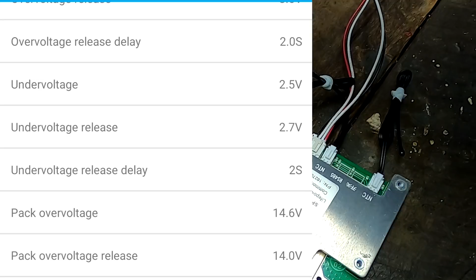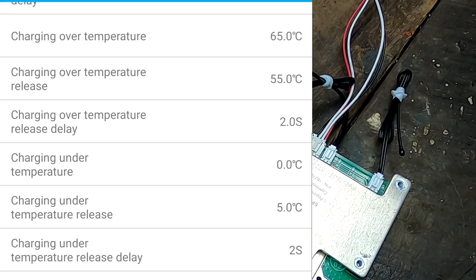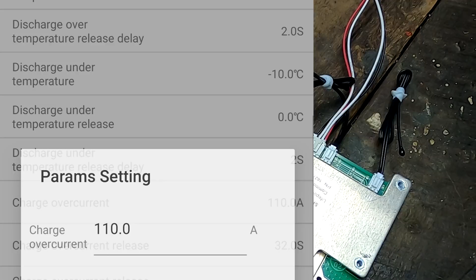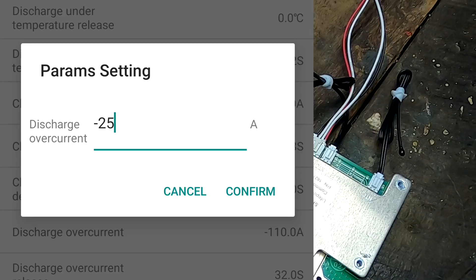14.6 is fine, that's 3.65 times 4, right? Pack under voltage 10 volts, 2.5 times 4. Temperatures, okay, we can have a look at the temperatures later on. Charge over current 110 amps - that should not be more than 3 amps. Discharge - and we don't want to pull more than 25 amps from this battery pack.